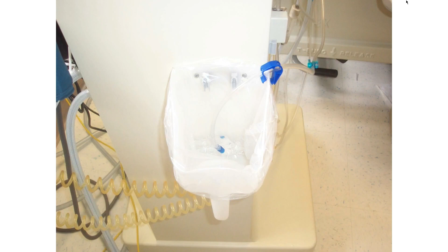It's during priming. Something with the bicarbonate of the wall box. No, it wasn't, but there's something else with that. No, it happened actually this way. You're all familiar with the priming buckets. The priming buckets have clips intended for a purpose. It's to make sure that when you clip the venous line into that effluent bucket, it's clipped as close as possible to the top. The reason is that as you're priming, the saline rises. If it rose to this point, guess what happens to the venous tip? It gets saturated with whatever organism or contaminant is in that bucket. You hook up that patient to that venous line, what happens? Direct inoculation of that organism. No alarm, but it happens.